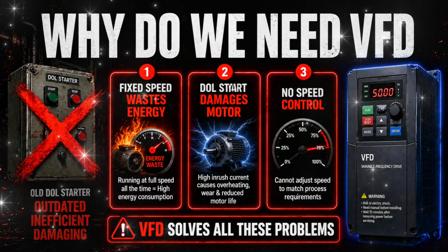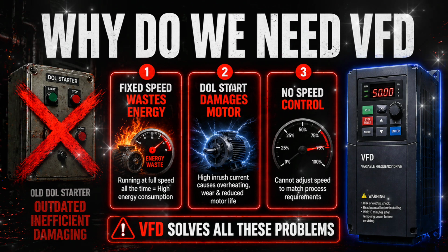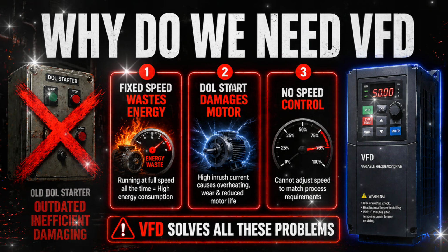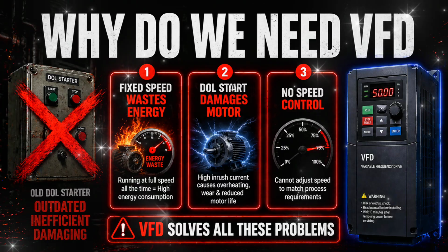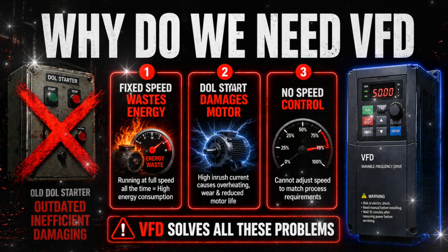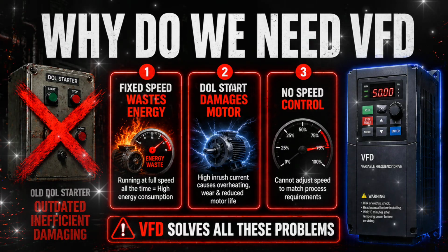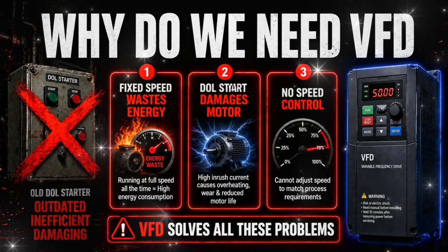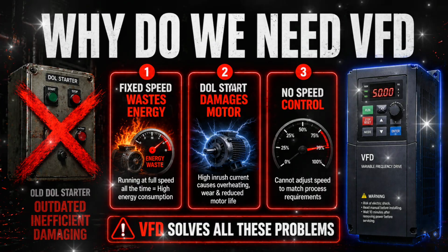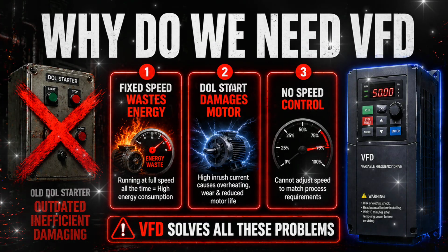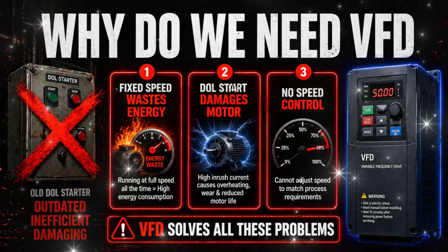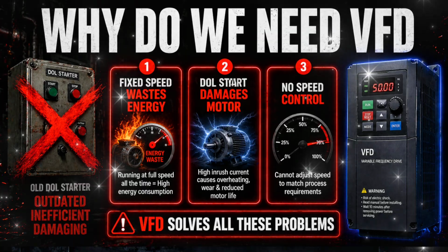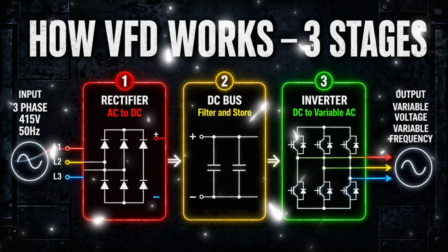Second, direct on-line starting causes huge current surge, up to 8 times full load current. This damages motor windings and bearings over time. Third, you have zero speed control. The process cannot be adjusted. VFD solves all three problems at once. This is why it is used everywhere in modern plants.